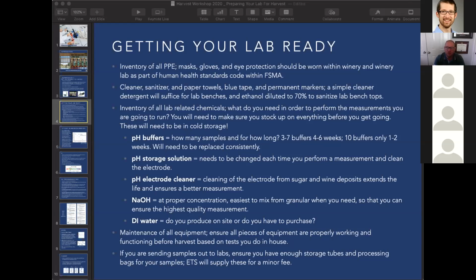So how long do buffers last? That's like a huge question that I get all the time. For buffers from 3 to 7, they last open for about 4 to 6 weeks. My recommendation would be to replace every month. So think about how many pH measurements you are doing. If you're doing pH measurements to determine pH increases during pressing, then you're probably going to use a lot more buffer. 10 buffers, only 1 to 2 weeks. So if you're using a 3-point calibration, so let's say you're 3, 7, and 10, or 4, 7, and 10, the 10 buffer is only going to last 1 to 2 weeks.